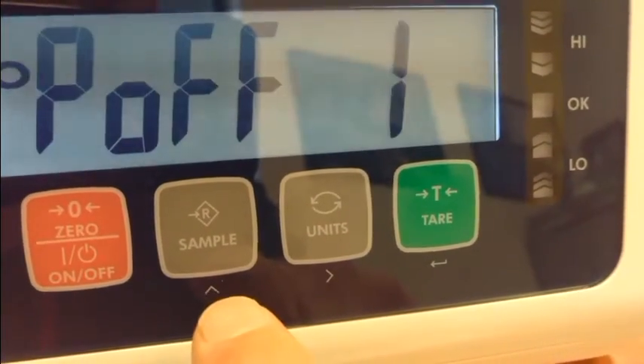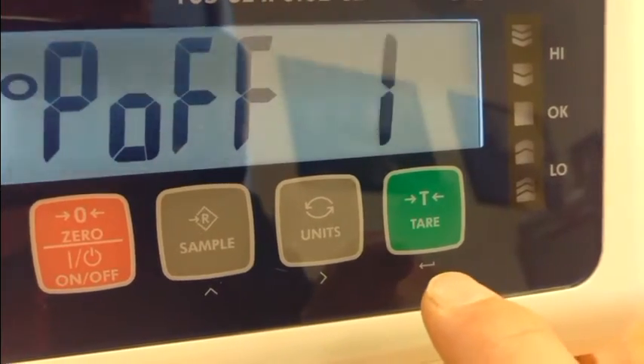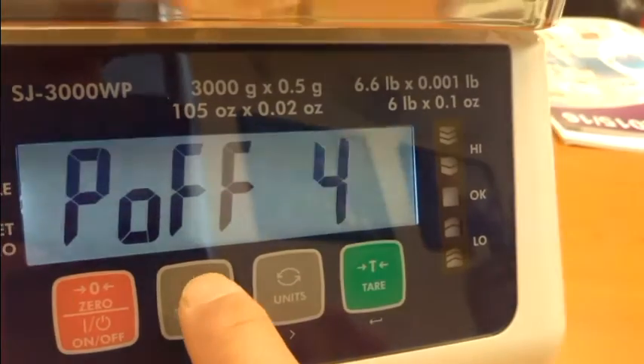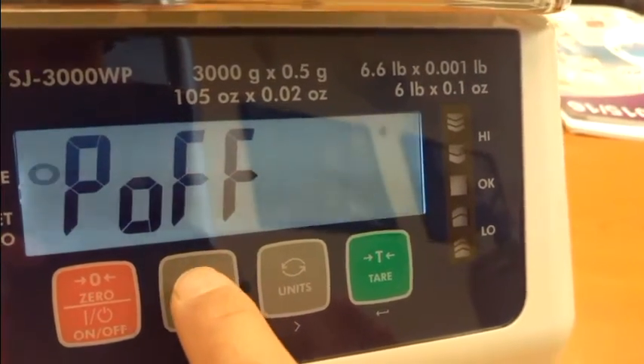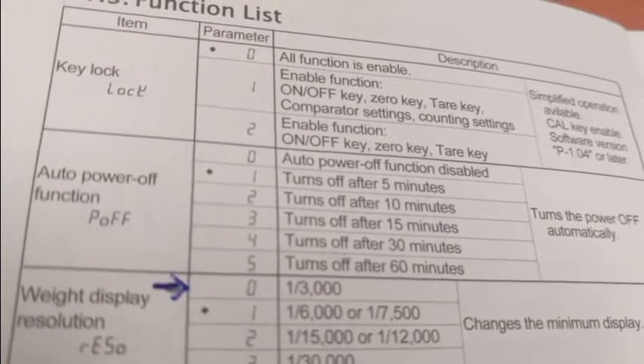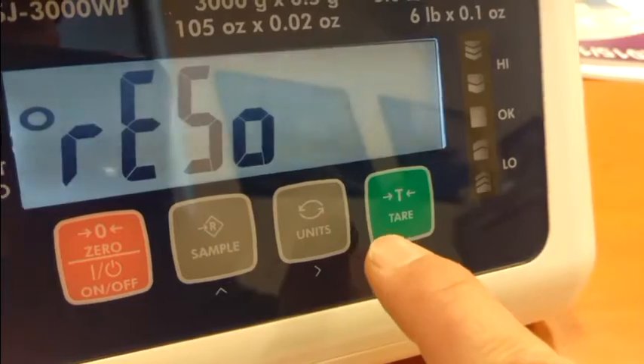Now these keys here, you can see the four buttons, basically three of them have a secondary function. Underneath this one you can see an up arrow, this one's got a right arrow, and this one's got like an enter symbol. What happens is if we press the up arrow that number changes to a different value. Refer to the instruction manual for the exact details. So here the power off function you can see you've got a setting of zero to five and we just want to leave it at number one. Then if we hit the right hand arrow it goes to the next setting.